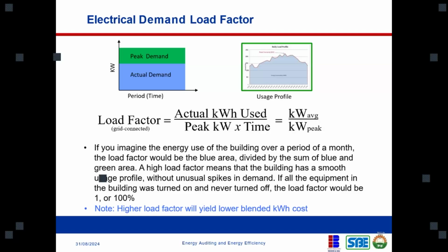And let me also add that for diesel generators, the minimum load factor that you can put on a diesel generator to still allow it to work well is 30%. Once you go below 30% on a diesel generator, it becomes harmful to that generator. It creates problems for that generator. And when we talk about solar systems, we'll talk about this as well, because for solar designs, in some cases, you have to integrate the generator into the solar system.